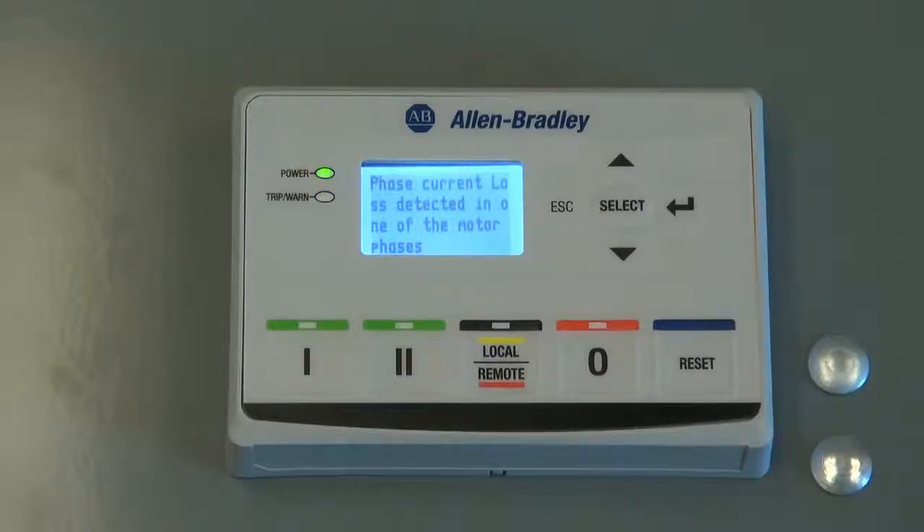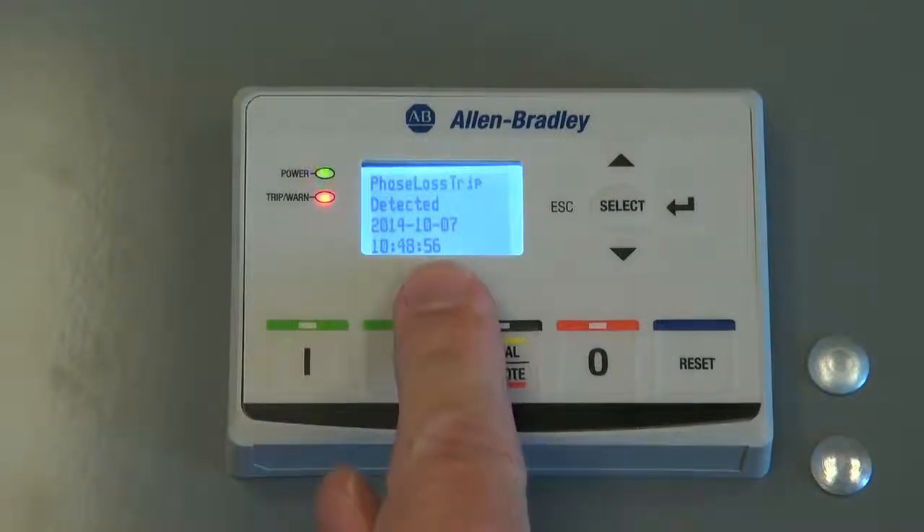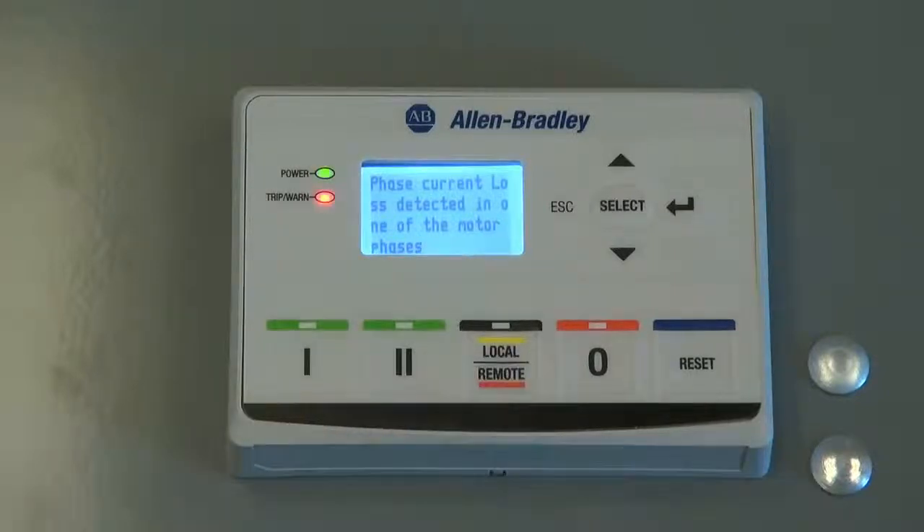In this example, the trip/warn LED is blinking a short, two-red flash pattern. This indicates that there has been a phase loss trip. The LCD display will also provide information for the reason for the trip. In this example, the LCD display is showing that there has been a phase loss trip.